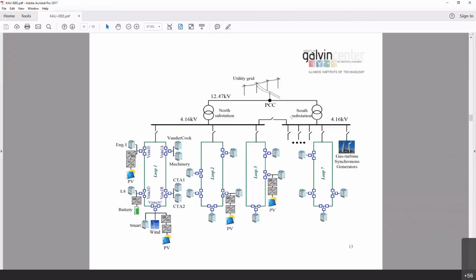There's a normally open switch between the two substations. If one substation is malfunctioning, I can close the switch and the entire campus will be supplied by the second substation. It's a great system. Ever since we built this microgrid, we have not had any downtime. We've had outages, but no downtime—basically, lights never go off in this system.